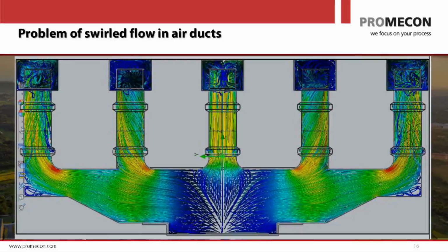And that's a big problem that our measurement does not have, because our measurement measures an air velocity vector, and the vector has a direction. We only measure the air in the direction of the duct. We don't measure the air velocity as an absolute value, but as a directed flow.